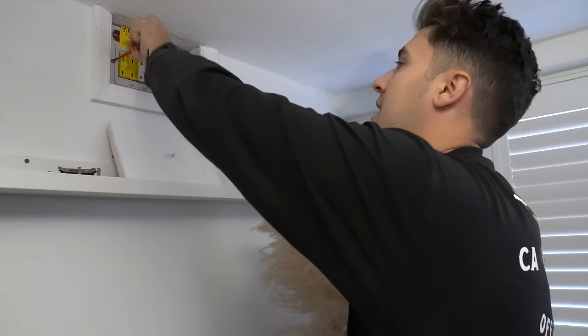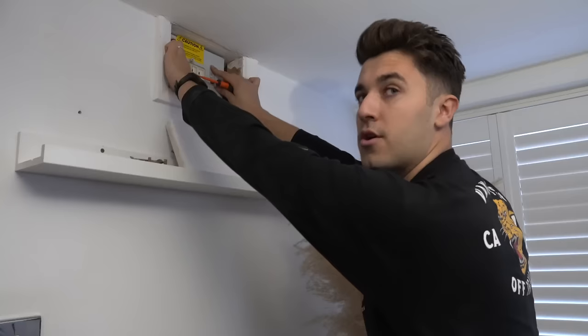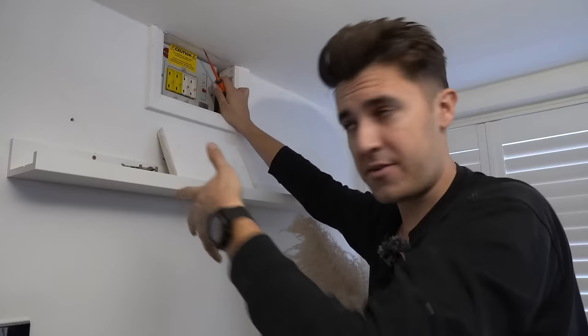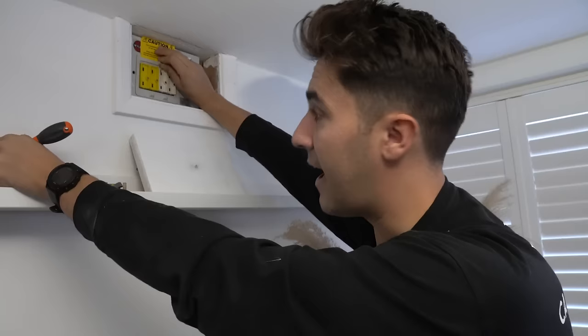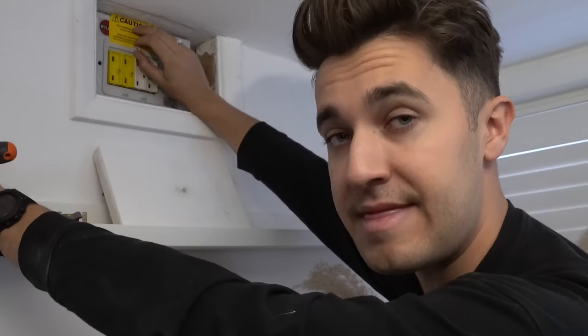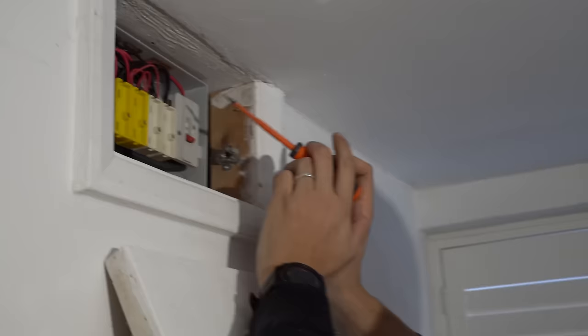Anyway, I've been getting calls from my beloved family saying that fancy device I put in has been tripping. Could be an extension lead, could be a variety of things, but it's definitely not a fault because this has been tightened up and tested. Everything in here is solid, and it's a piece of kit from the 80s — everyone knows stuff from the 80s is solid. MEM and Wylex fuse boxes. However, that arc fault detection device might have just saved this house. That is absolutely terrible. That is a fire on a stick, a fire waiting to happen.